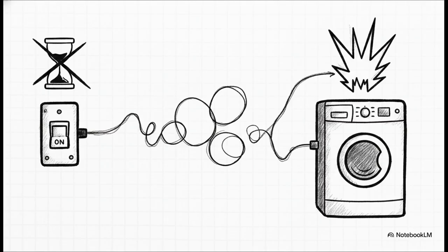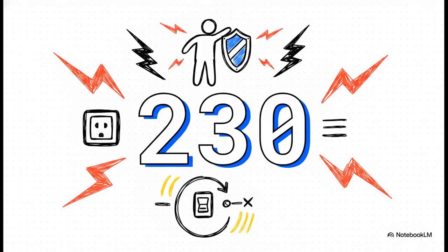So, here's the catch. If your earthing wire is too thin, or maybe it's just way too long, Zs goes up. And if Zs goes up too high, the whole formula breaks, meaning that breaker won't trip in time. And here is the constant in that formula, 230. 230 volts is the nominal AC voltage to Earth in our region. So the crucial point is that your protective device must operate and cut the power way before this 230 volts is allowed to just sit on an exposed metal surface long enough to become lethal. The total resistance of your earth loop multiplied by the trip current can literally never exceed this 230 volt threshold.